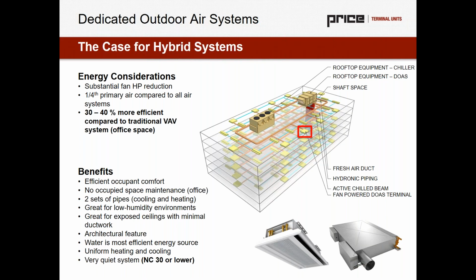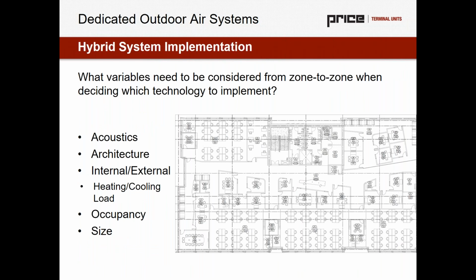And I want to close this off with a bit of an example, and I want to go through the idea of where would we place this equipment within zones? So what I want to look at is this floor plan here and consider, zone to zone, which technology do we implement? And what do we consider? Well, of course, we consider those acoustics, with chilled beams potentially being a bit more quiet, or at least definitely more acoustically flexible. Architecture is huge, so maybe we want a chilled beam style of ceiling, and that pleases the architect's eye, it pleases the building owner's eye. But maybe we also want fan-powered terminal units because they're more architecturally flexible.